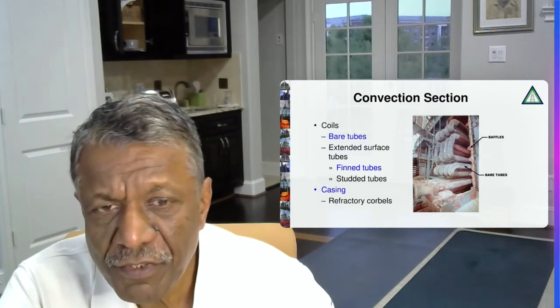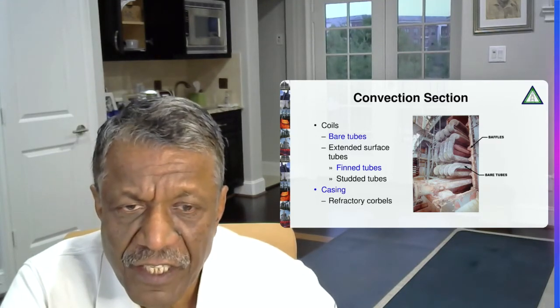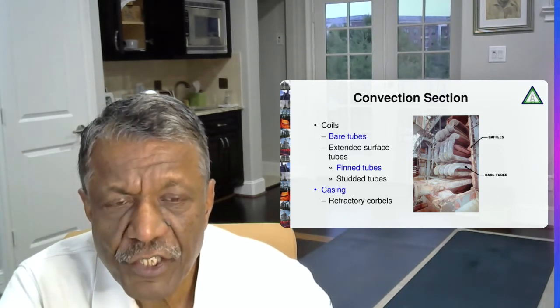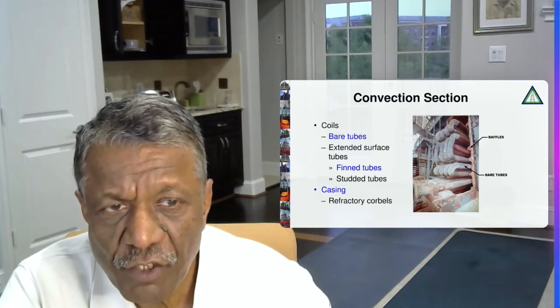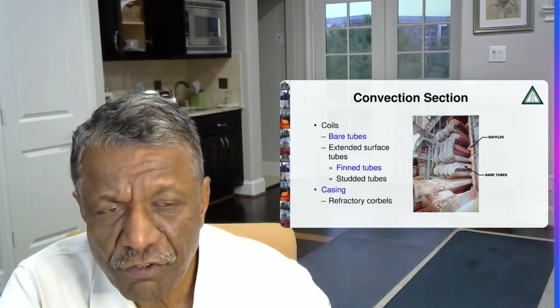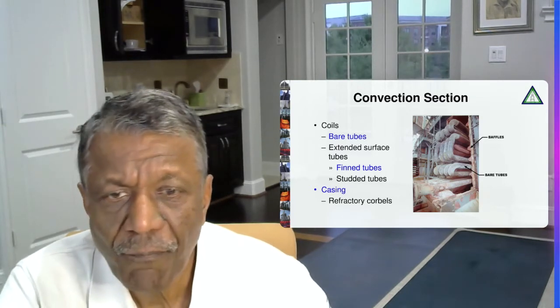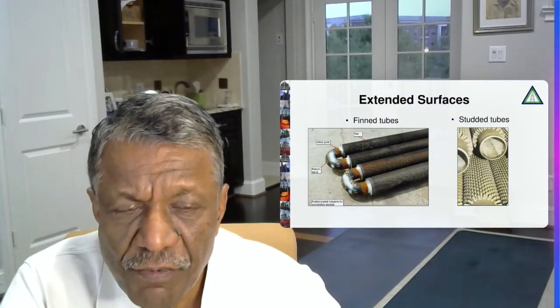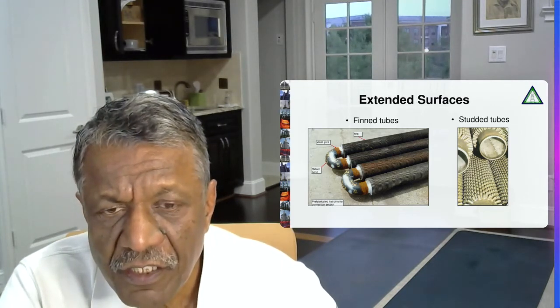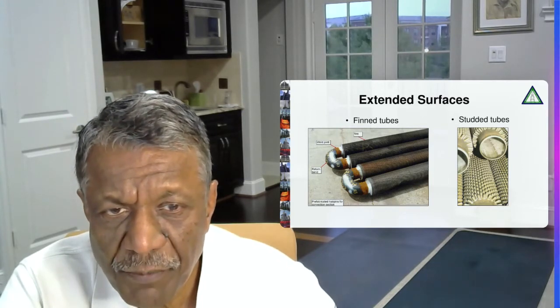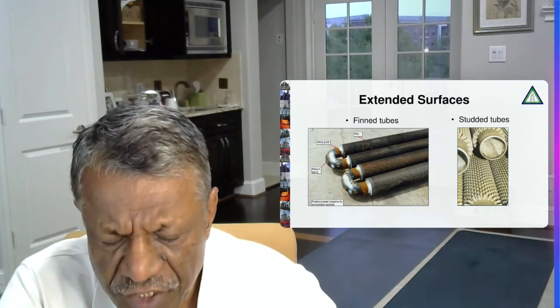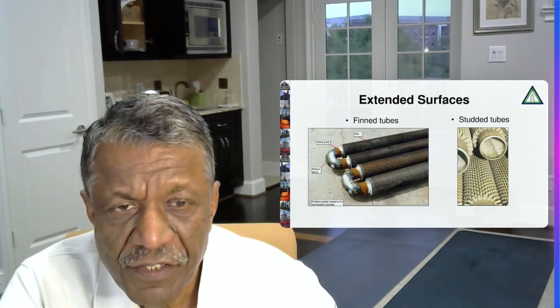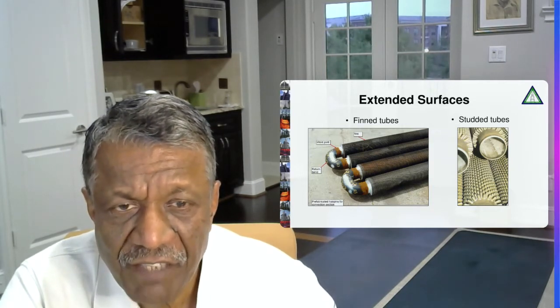The extended surface could be fin tubes or studded tubes, and then we have the steel casing on the outside and the refractory corbels. Refractory corbels or baffles are needed because we have the tubes arranged in triangular pitch. And because of the triangular pitch, since they are staggered, we need to put corbels in alternate rows on each side to prevent the flue gas bypassing. Here the fin tubes, you can see the fin tube and the studded tubes. The fin tubes are solid fins that is used in fired heater industry. Typically we use only up to 5 fins per inch and 1 inch height. Fins can increase the heat transfer area of the tube by anywhere between 6 to 10 times. So fins are very, very efficient. And because of fins, the convection section sizes have come down.